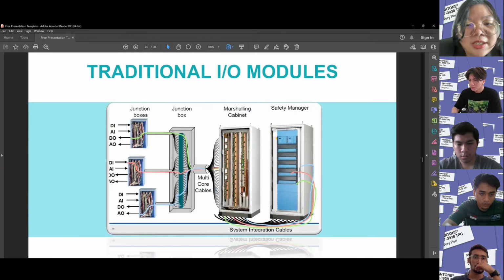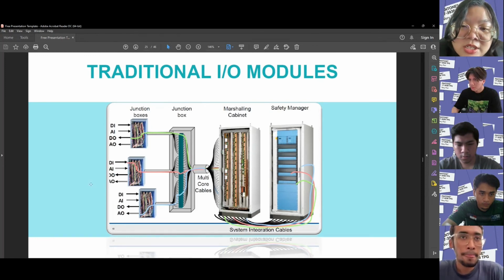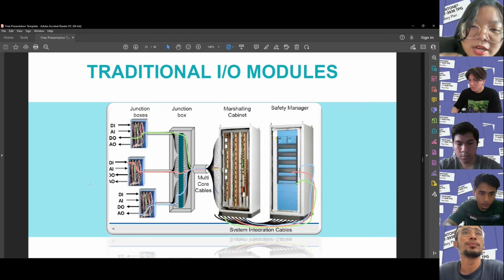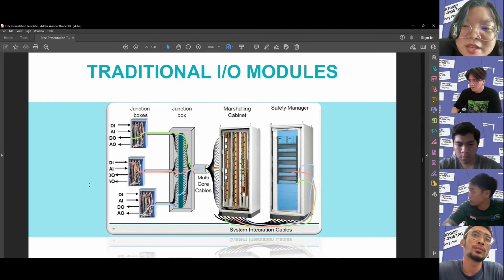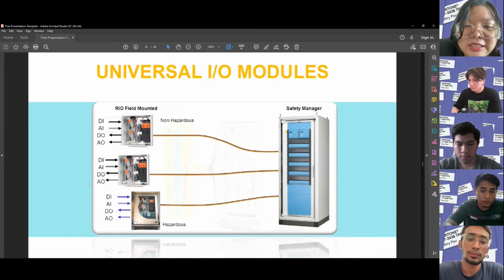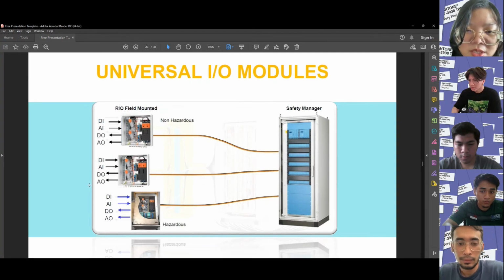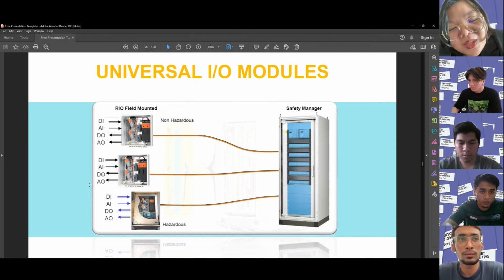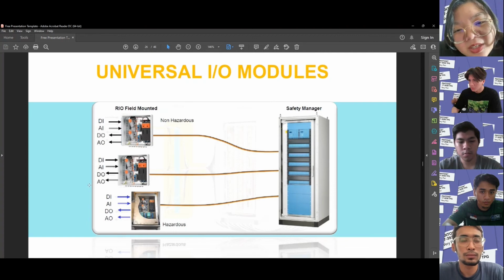Okay, this is an example diagram of traditional I/O modules. It consists of junction boxes, there are three junction boxes and then one big junction box, and then the marshalling cabinet and the safety managers. This is the diagram for the universal I/O module. It consists of RIO, field mounted, which consists of the non-hazardous box, and a safety manager. Thanks.